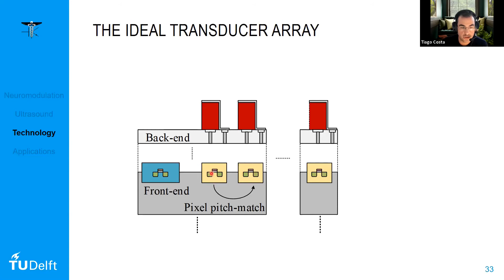So how can we move forward? What I have here is, for me, the ideal transducer array, and I'll try to explain now what's missing from the current version. So you see here the CMOS chip with the transistors and the back end where the connections are made to the piezos. There's first a very big aspect ratio. In between the pillars, there's normally 30 micrometer spacing or 50 micrometers, depends on the blade, and around a 100 micrometer pitch.